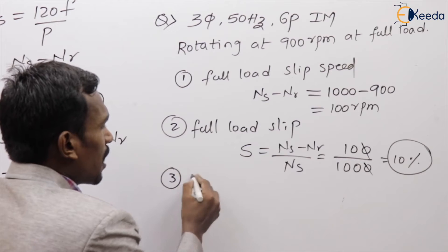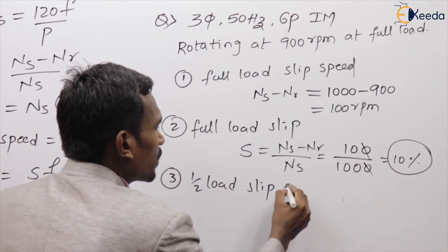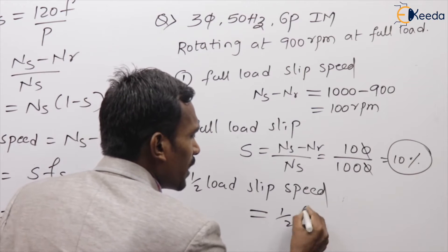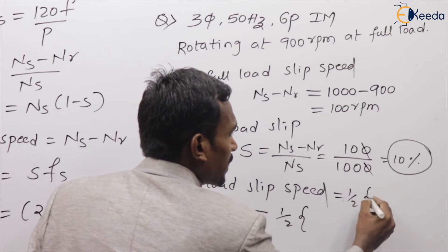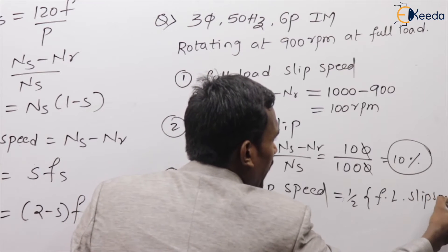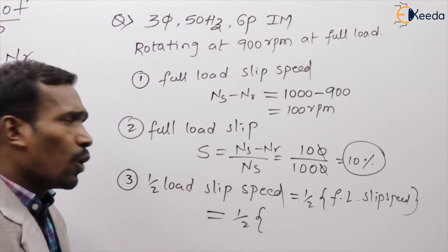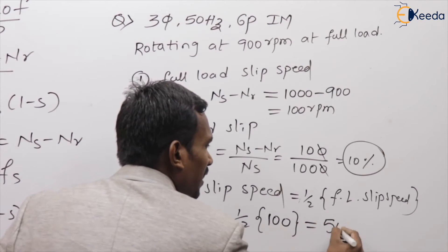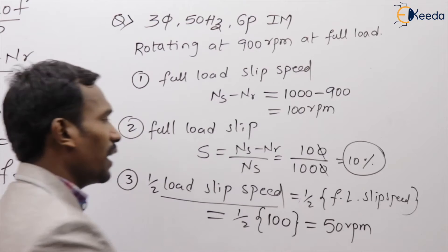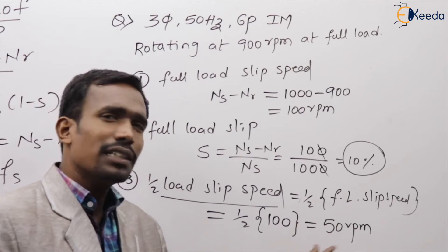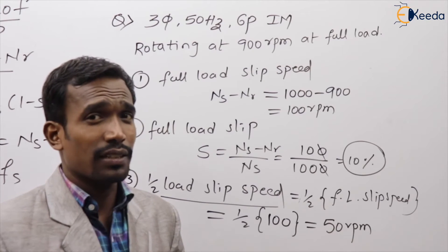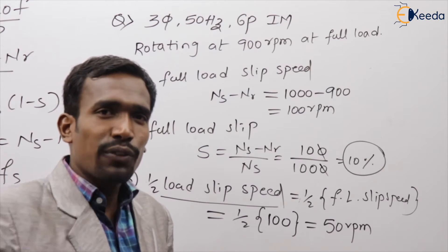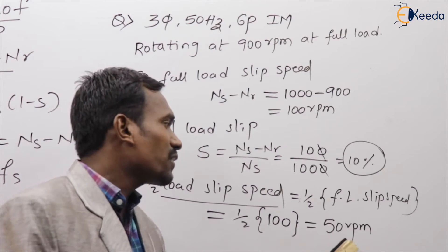Third question: what is the half load slip speed? The Xth load slip speed equals X into full load slip speed. Here X is 1/2 and full load slip speed is 100 RPM, so half load slip speed equals half into 100 equals 50 RPM. At half load, just 50 RPM is slipping.